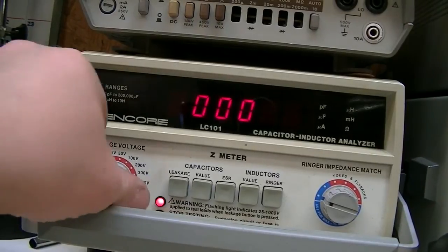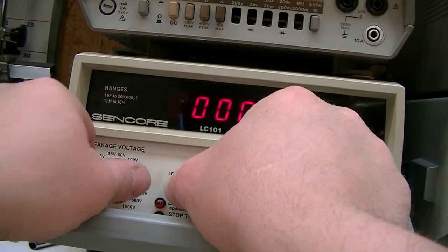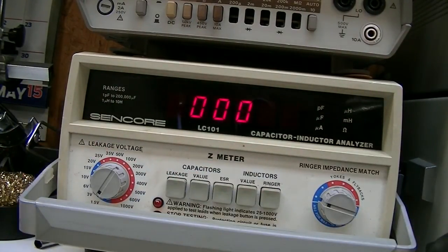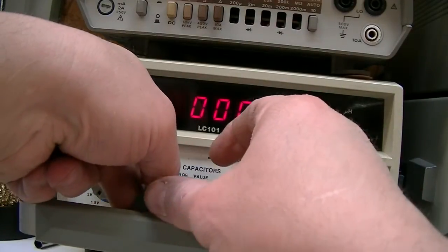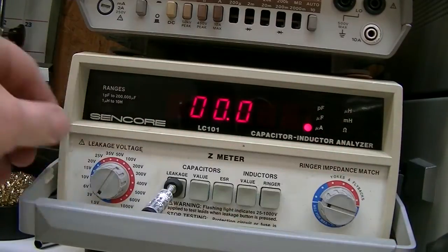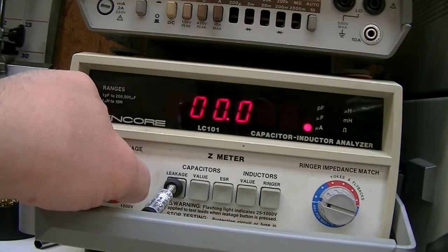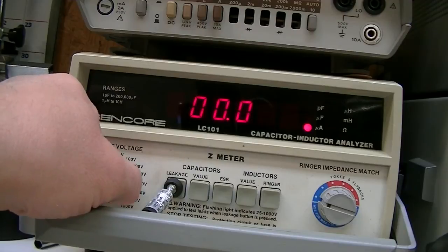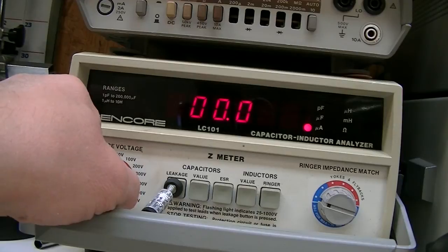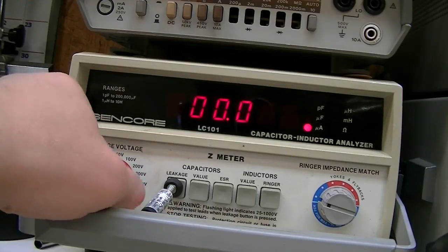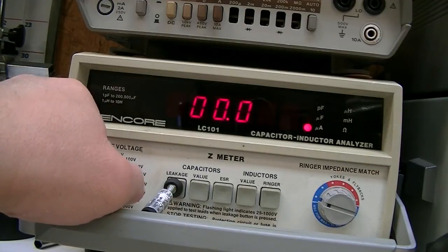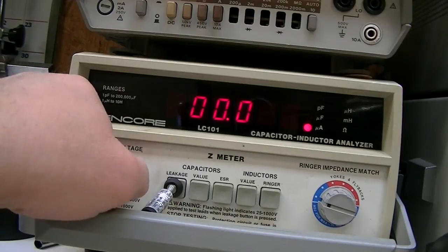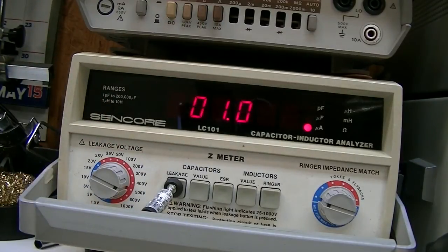So, I'm just kind of curious. I'm going to ramp back up again on this one. We'll see. Where's my little stopper at? Put that in here. There's 100 volts, 200, 300, 400, 500, 600, and there, that time it broke at 1000. So, that's pretty intermittent.